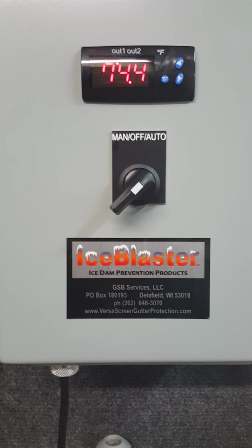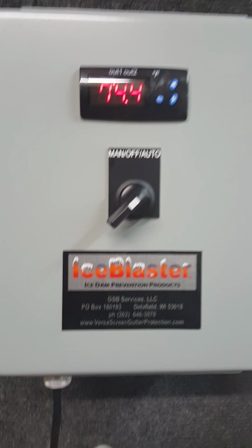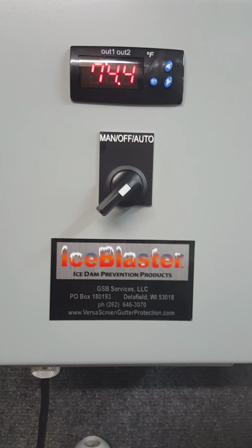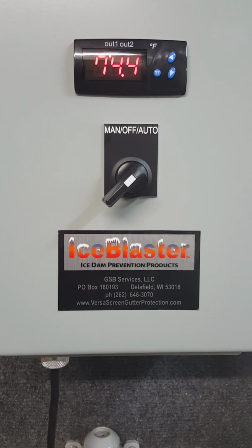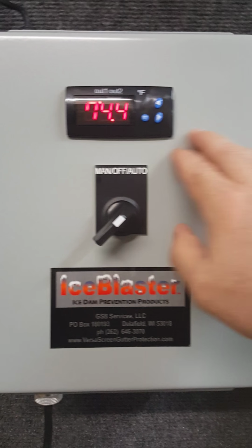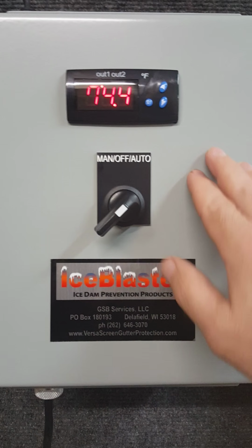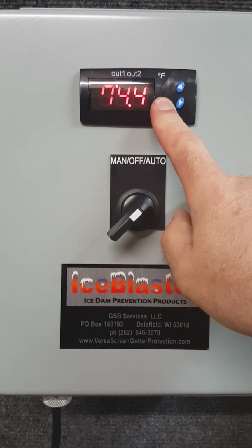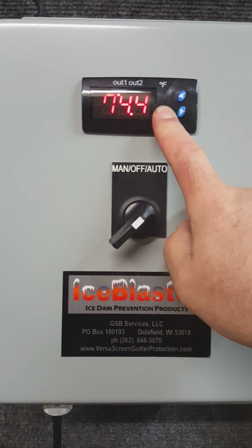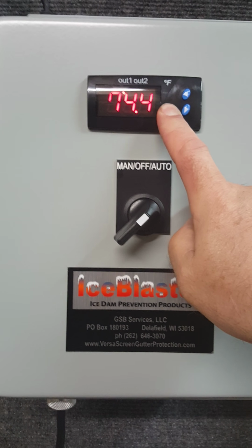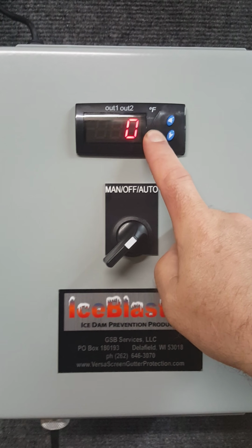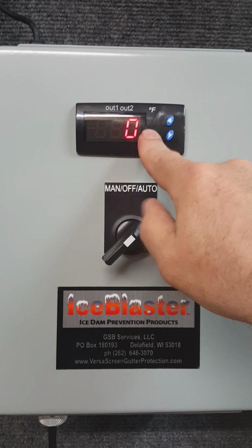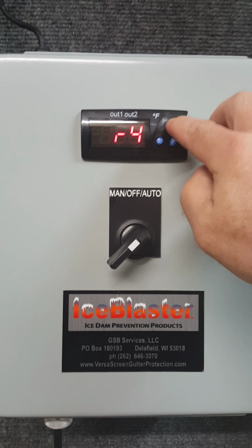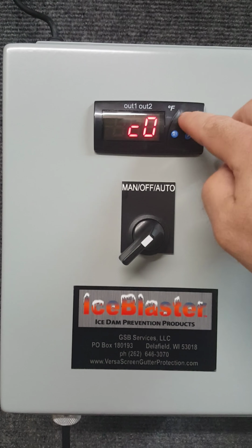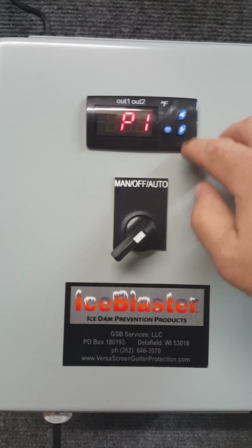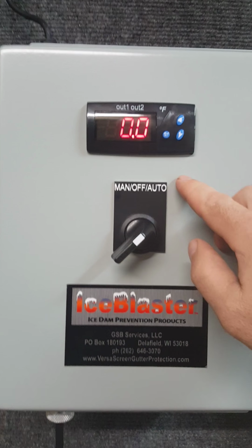Now, let's say you're having a little problem with the calibration. Perhaps where you've set the thermistor, maybe the house is emitting a little bit of heat, and the actual temperature this is reading is maybe 5 degrees warmer than what it actually is outside. Well, we've got the ability to set that calibration, or to calibrate the controller here. And that's done, I've held it down about 8 seconds, hit set again, and then we can arrow up to the setting. And the calibration setting, we want it on probe 1, calibrate.